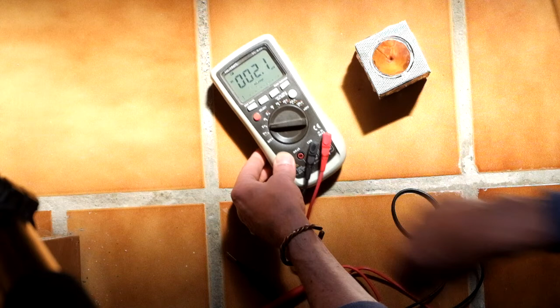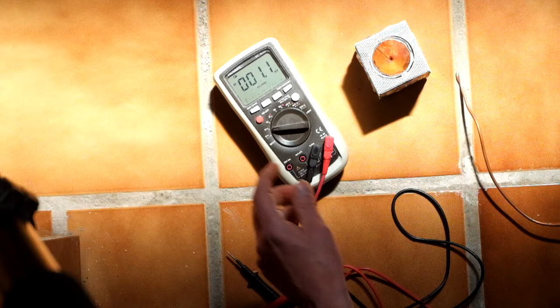Now I go on direct current again, and what happens when I ground that device now on a real ground, because I used my body as ground before. So I prepared here a wire, and I now connect that to the casing of the device, and I press the casing towards that wire with the one probe. You see already the value is rising because the device is grounded.